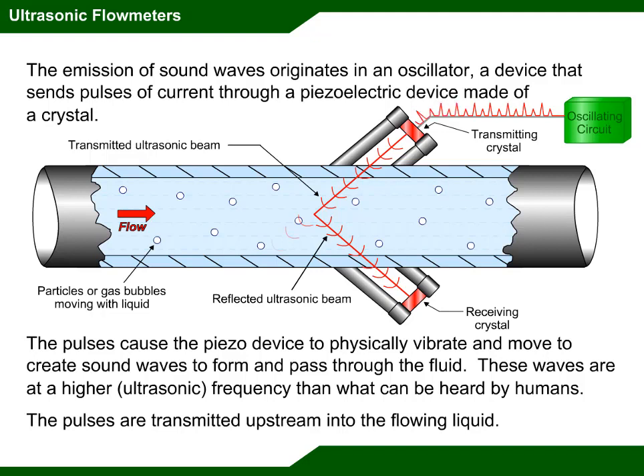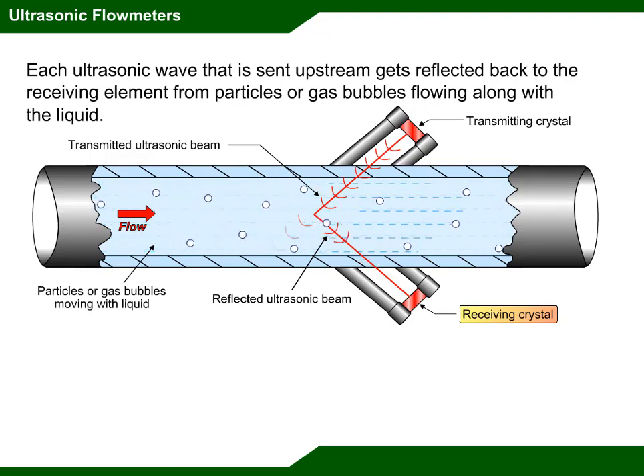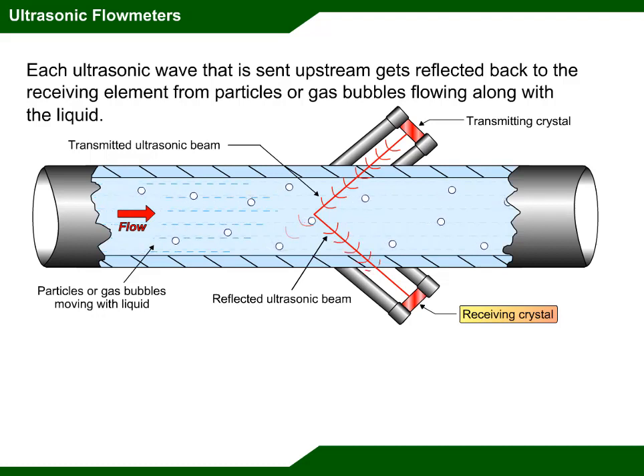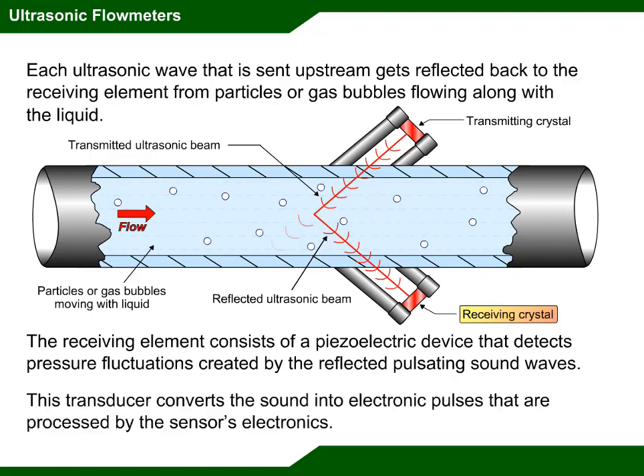The pulses are transmitted upstream into the flowing liquid. Each ultrasonic wave sent upstream gets reflected back to the receiving element from particles or gas bubbles flowing along with the liquid. The receiving element consists of a piezoelectric device that detects pressure fluctuations created by the reflected pulsating sound waves.